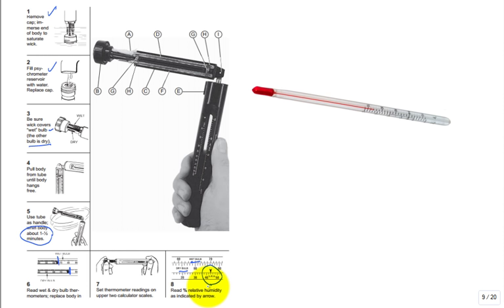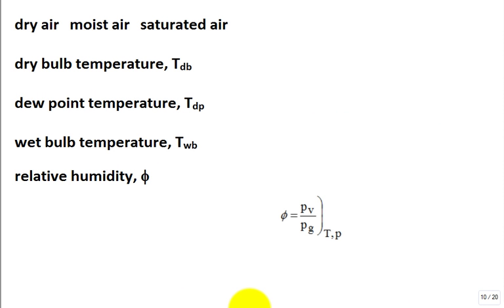These devices are still used in practice, though they've mostly been replaced by electronics — an instrument technician can bring something in and digitally read out dry bulb, relative humidity, and wet bulb. If you call campus facility services and complain your room is uncomfortable, they'll check the temperature first. If you're complaining about stickiness rather than temperature, they'll bring out a sling psychrometer and check the humidity.